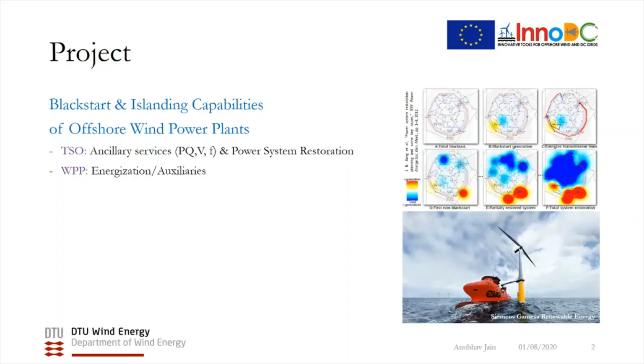As far as the wind power plant operator is concerned, right now wind turbines rely on auxiliary sources, mainly a diesel generator on the offshore substation, for energizing the offshore network cables, transformers, and even creating the offshore collector grid when the main grid is out. This diesel generator is associated with large costs due to the space it occupies offshore, maintenance requirements, shipping related downtimes of about 3 to 6 months, insurance costs due to an extra fuel tank, backup diesel generators, and safety constraints.